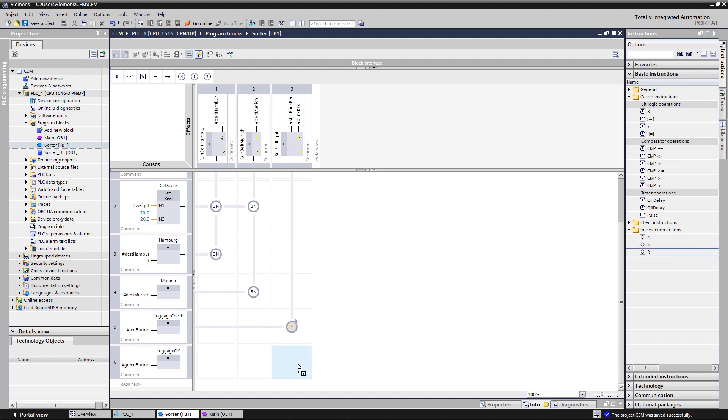At the intersection of cause 6 and effect 3, the action R for reset is programmed. Its effect is that the lamp stops flashing when the green button is pressed. In addition, stat blink red is reset. Now we have implemented the interlock for the small application.